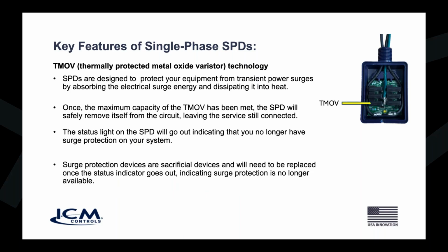Now you can see from the diagram there on the right, the TMOVs are those little black boxes in there, and you can see two banks, and this is the 517A Lite. There are two banks of three there, so you've got about 60,000 amps of protection there for a single hit, and multiple hits under 60,000 amps. It's important to note here, these are not a one and done product. Just because we say that when SPDs reach their limit they have to be replaced, doesn't mean they're going to reach their limit in one hit.